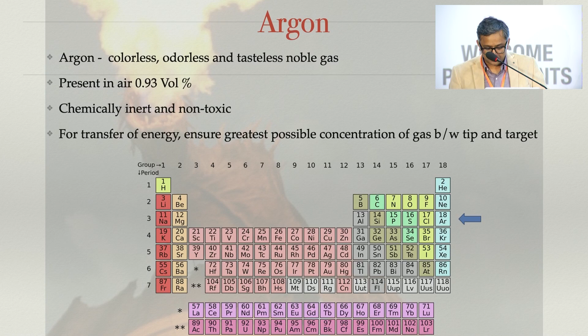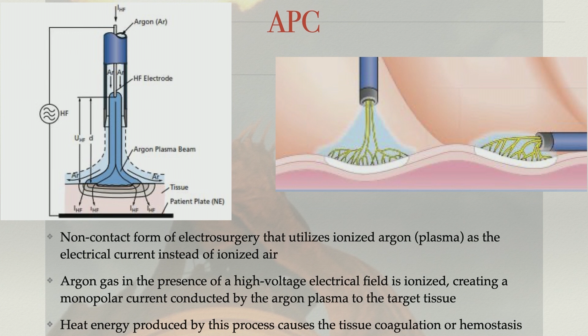The presence of a high voltage electric field is ionized, and it basically creates a monopolar current which creates this particular transfer, and heat energy is produced causing coagulation and hemostasis. The principle is: extracellular water gets evaporated and it denatures the protein in our tissues, and that basically leads to the destructive effects that APC produces.